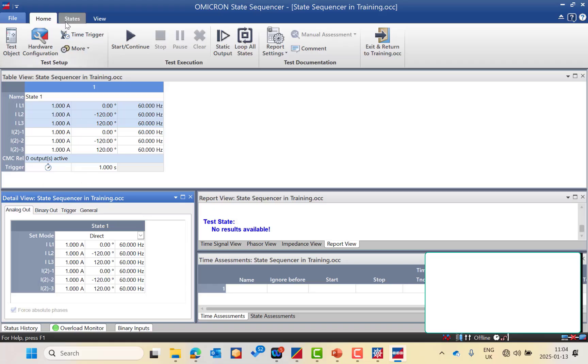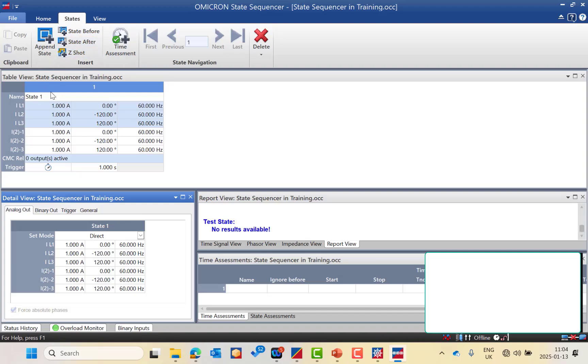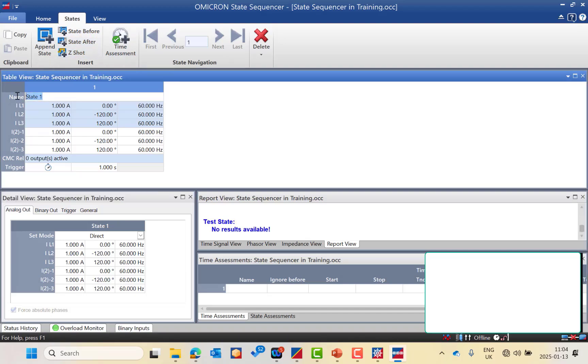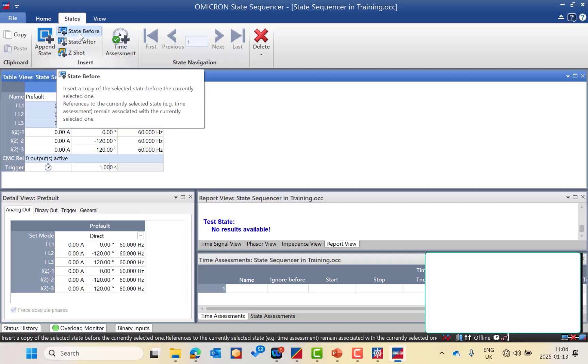As you can see, I can add a state after or state before. This first state will be the pre-fault state. I will specify this current to be 0 or 0.1 A — equal magnitude — and the same for the others. Here is the time of the pre-fault state; you can set it to one second as needed.